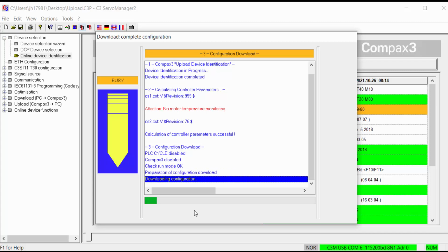If it's a T30 or T40, it would also download the .pro project code assist file, and what actually gets downloaded is the compiled binary file and also the CAM profile. You do not need code assist installed to do this, so you don't need to install code assist, you don't need to install the targets.